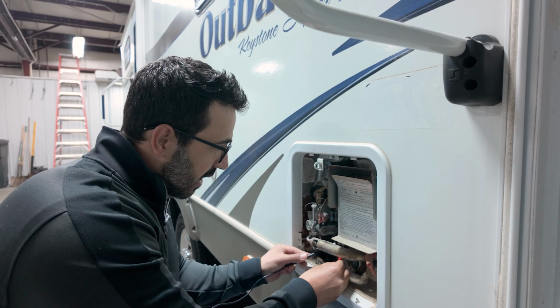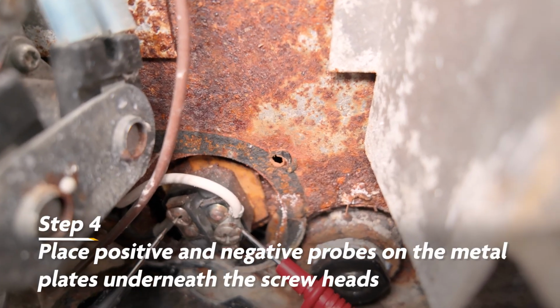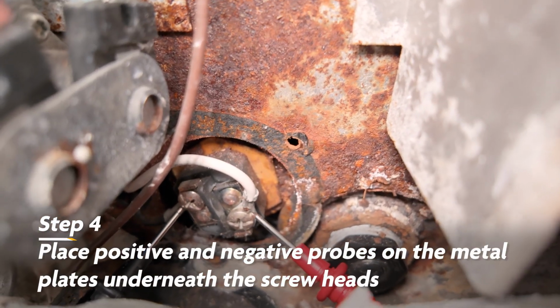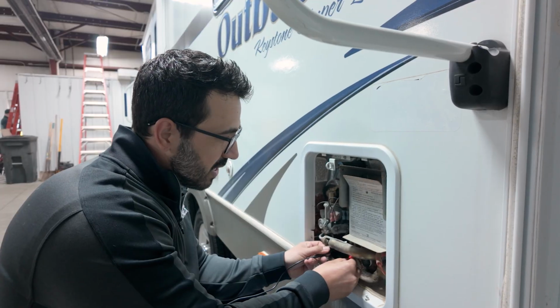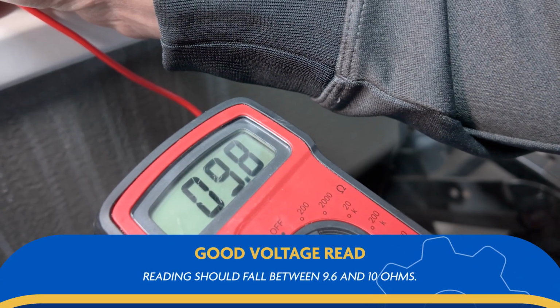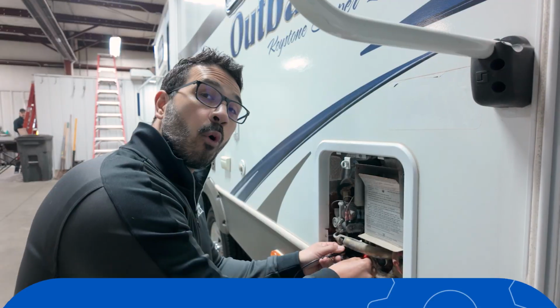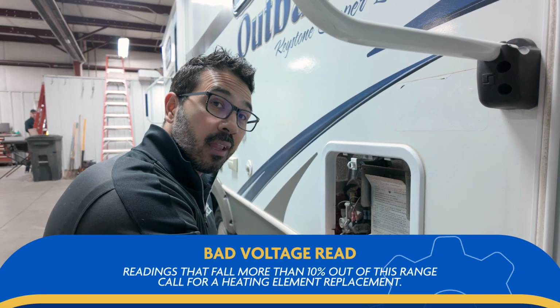So once we find the heating element, we want to take our probes and we're going to put them on the metal plate right here underneath the screws that are securing that heating element. It should read somewhere between 9.6 and 10 ohms. If it's reading less than 9 or more than 11 ohms, then you have a bad heating element.